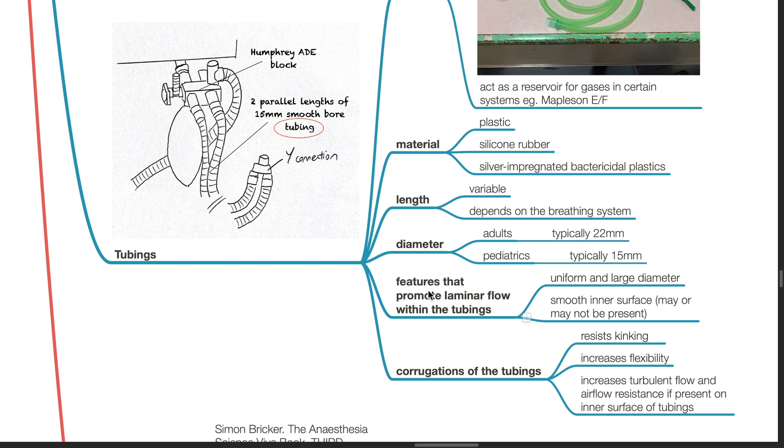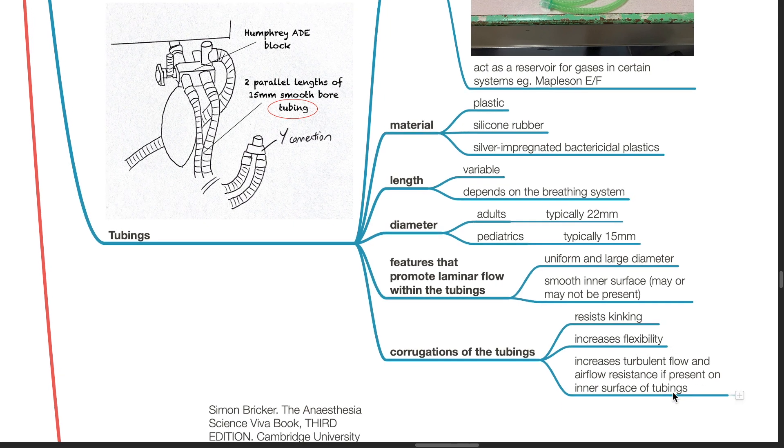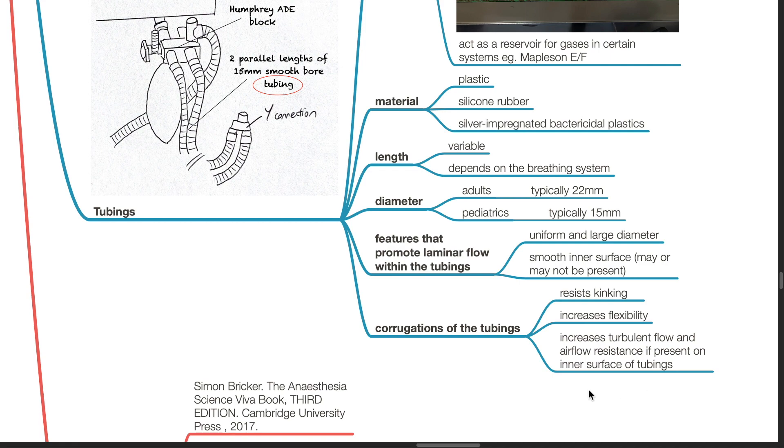Features that promote laminar flow within the tubings: uniform and large diameter, smooth inner surface. Corrugations of the tubings resist kinking, increases flexibility and increases turbulent flow and airflow resistance if present on inner surface of the tubings.